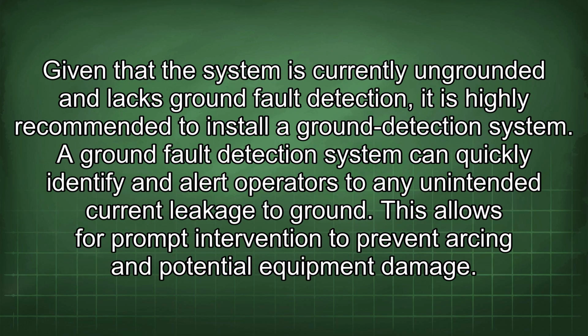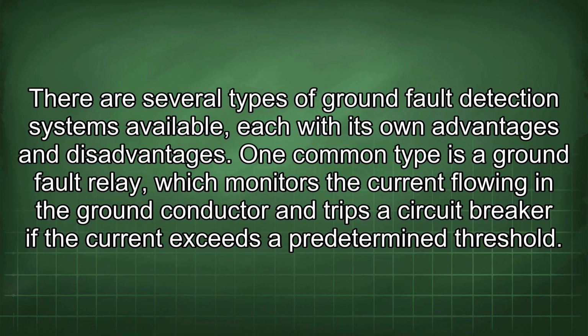Given that the system is currently ungrounded and lacks ground fault detection, it is highly recommended to install a ground detection system. A ground fault detection system can quickly identify and alert operators to any unintended current leakage to ground. This allows for prompt intervention to prevent arcing and potential equipment damage. There are several types of ground fault detection systems available, each with its own advantages and disadvantages.